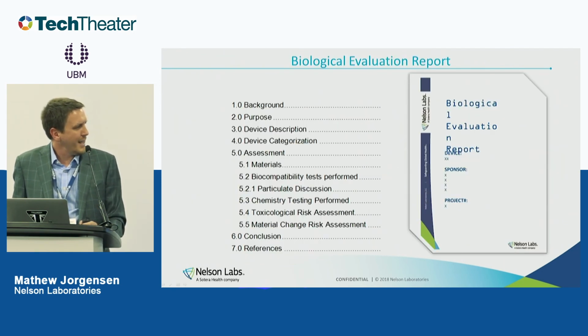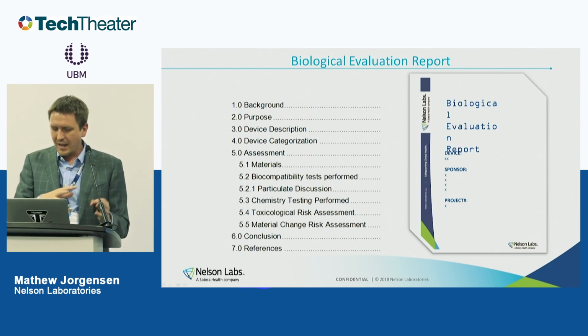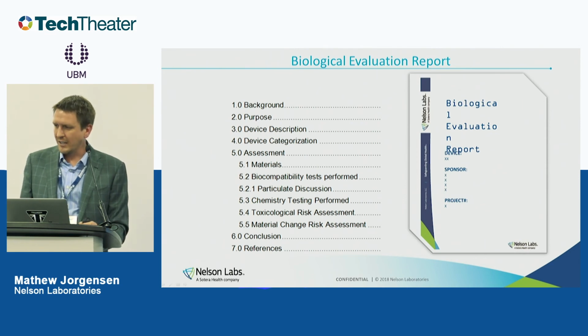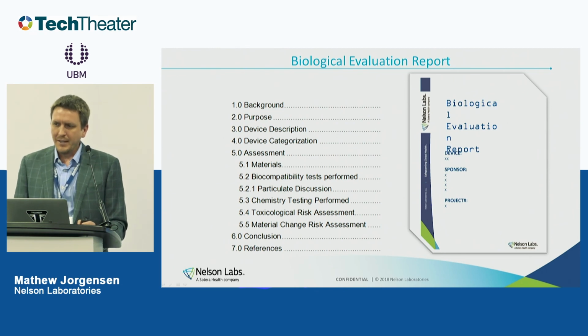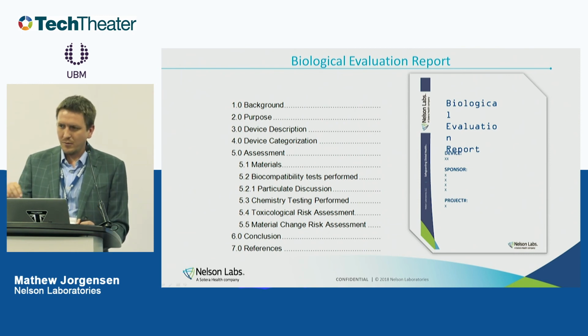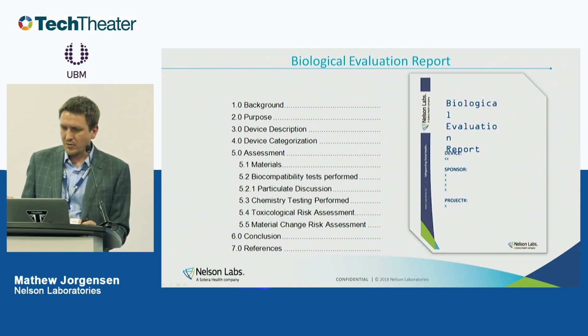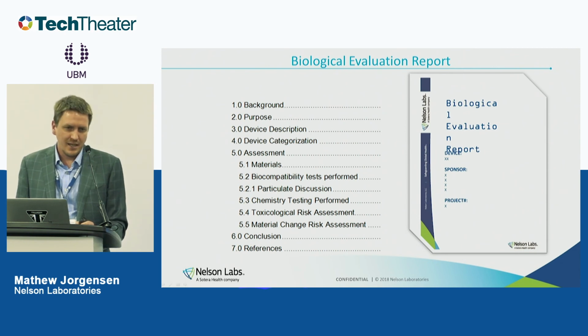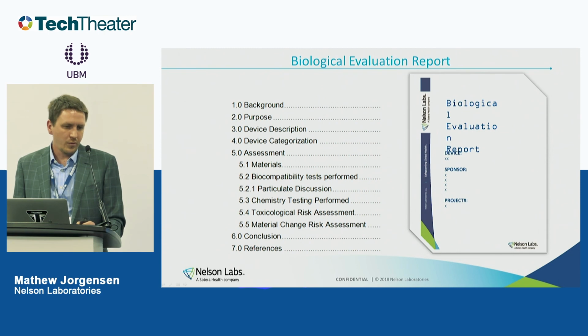Okay, and then finally, after you've made the plan and done the testing and the evaluations, I should really say evaluations and, if necessary, testing, then you have the biological evaluation report. Like I said, this is a document that you may or may not have been used to preparing, but you sum up all the evaluations that were completed. Then there should be a conclusion, signed by an expert or somebody qualified to make this claim: this device was evaluated for compliance, everything passed, all the evaluations turned out good, therefore the device is biocompatible. That makes it really easy for your reviewer to go through and understand your point of view.